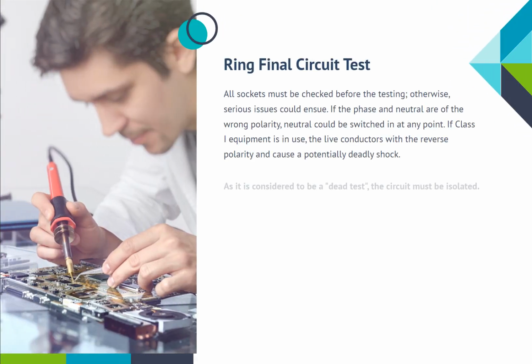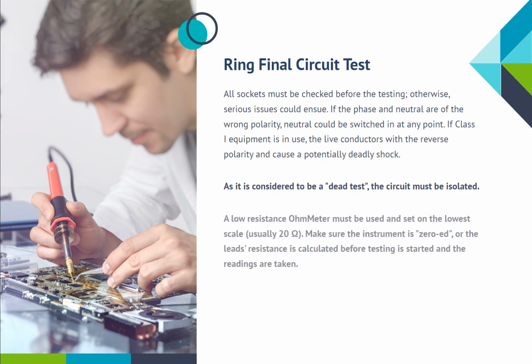All sockets must be checked before the testing, otherwise serious issues could ensue. If the phase and neutral are of the wrong polarity, neutral could be switched in at any point. If Class 1 equipment is in use, the live conductors would have reverse polarity and cause a potentially deadly shock. As it is considered to be a dead test, the circuit must be isolated.